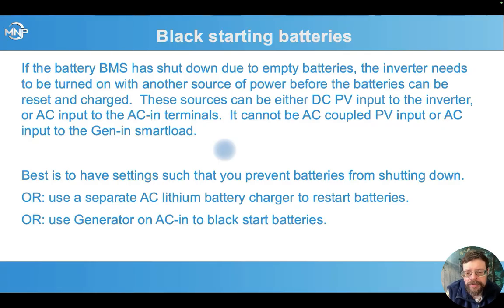Or we can use the generator on the AC in terminals to black start the batteries. That's if we've already got those all programmed with proper parameters so it will accept generator power through those terminals. So kind of two options there to black start the batteries from an AC source, a generator, when we don't have PV and we've accidentally gotten to the point where our battery BMS has shut down completely.